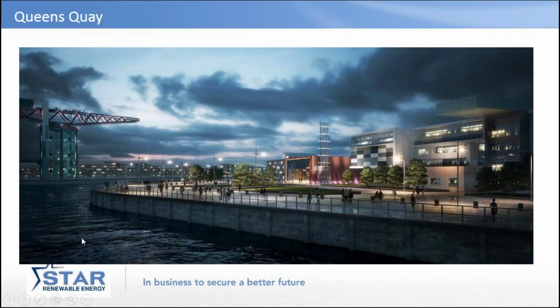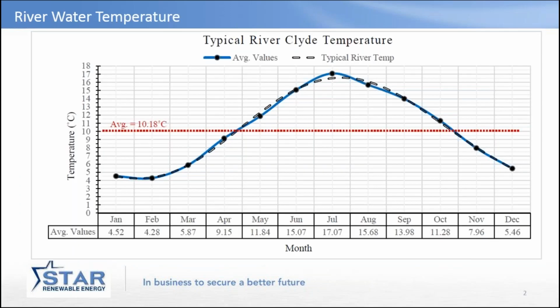I did a calculation recently. There's 200 megawatts of available heat from the river based on the flow rate of the river. And of course, this is the tidal part of the river, so really the tide is washing in from the Irish Sea and the Firth of Clyde. It's not totally inappropriate to say it's an infinite capacity of heat, certainly in the context of how much you might need. 200 megawatts would be a lot for any city. The temperature does vary, not terribly much, maybe from about 4 degrees up to about 17, and again, not terribly often up there, but the average temperature is about 10. So certainly not as warm as the air, but it's very, very consistent.